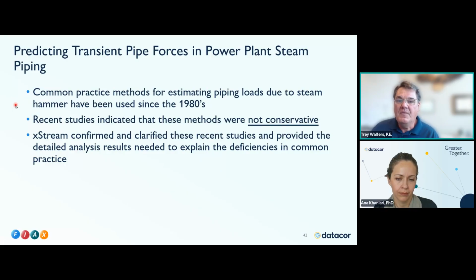Okay, so pipe forces in steam piping. Common practice methods for estimating piping loads due to steam hammer have been used since the 1980s. They've been used to model lots of power plants, probably almost all the nuclear plants we have out there. Recent studies indicated that these methods were not conservative. I'll show you what that looks like. xStream confirmed and clarified these recent studies and provided the detailed analysis results needed to explain the deficiencies in common practice. This should alarm everybody who deals with high pressure, high flow steam applications and is looking at pipe supports.